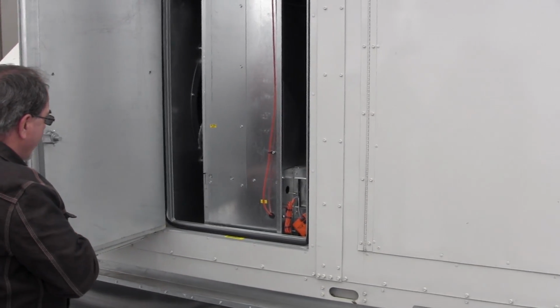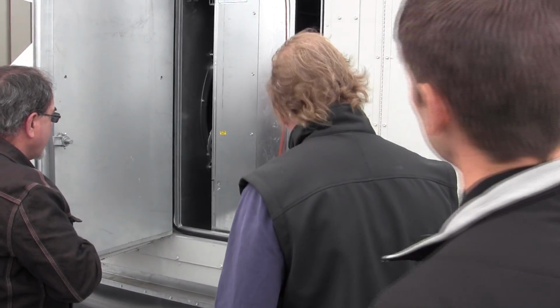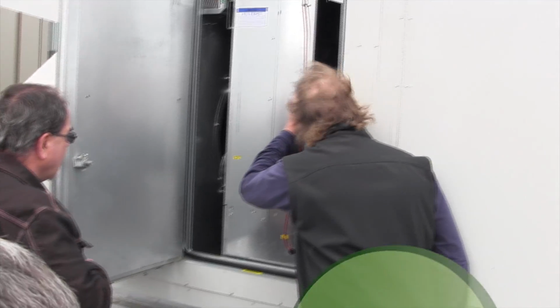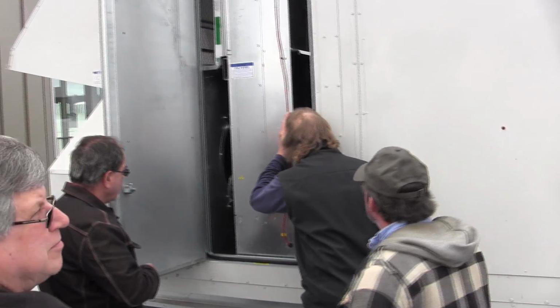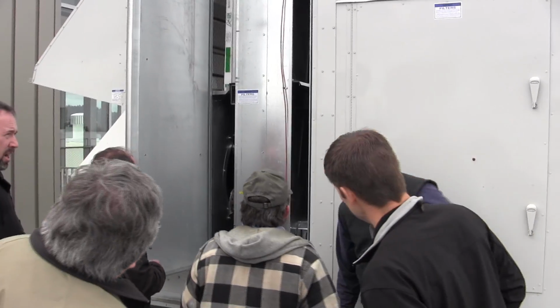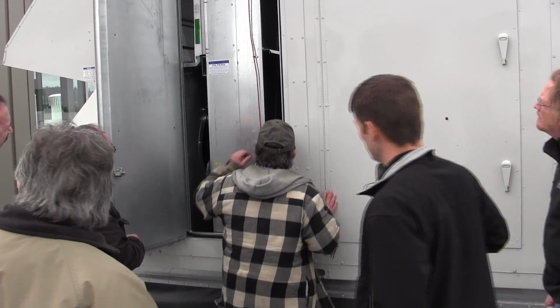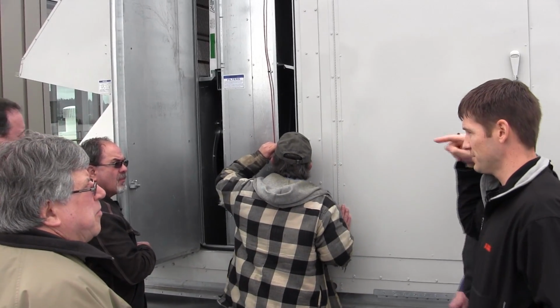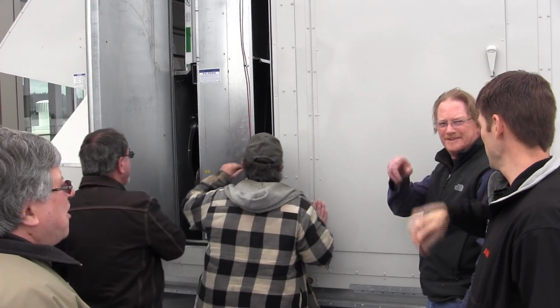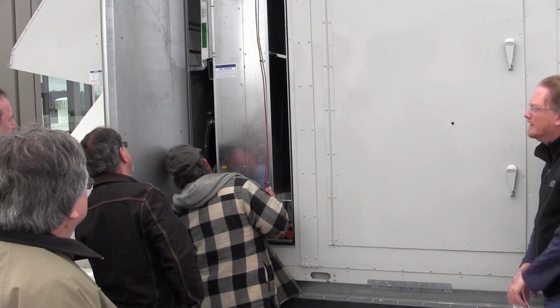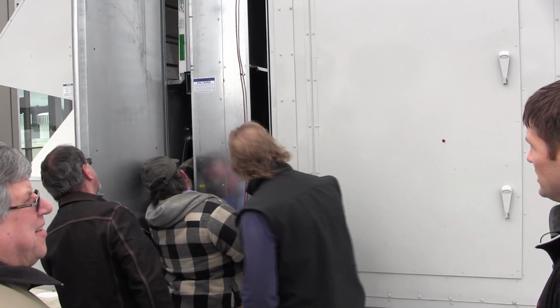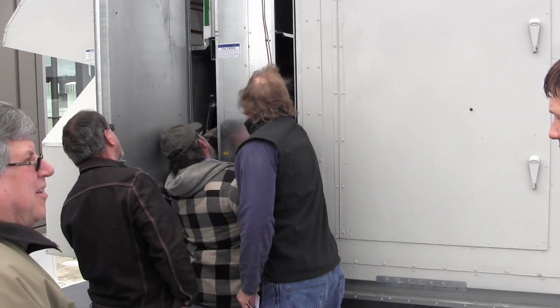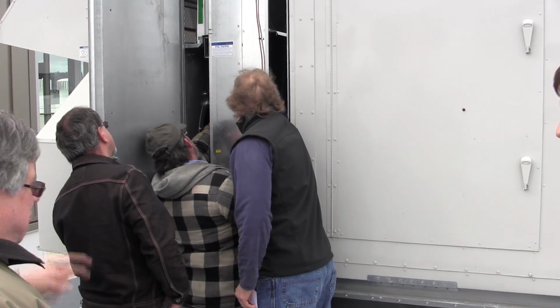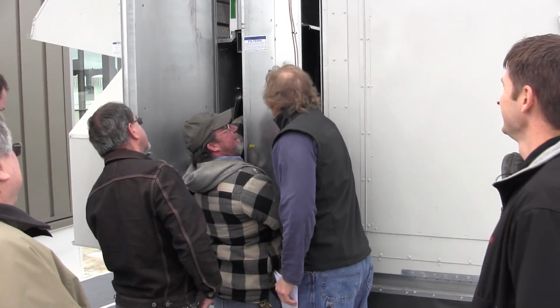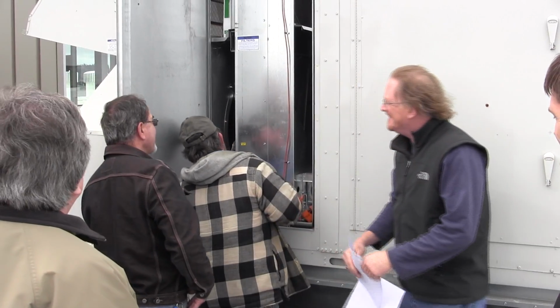That stop it? Yeah. So I just turned off the binary output from Automated Logic that controls that start stop, so the unit can keep running. If you put your finger in there and wiggle it, you can actually get your finger to go through it, like those pieces of paper, like a broom almost. They're pretty resilient. It's not like you're going to bend them. They just bounce back. Not like a coil fin. You can do that with a coil fin too, right? Yeah. Pretty fast. Cut your cuticles off.